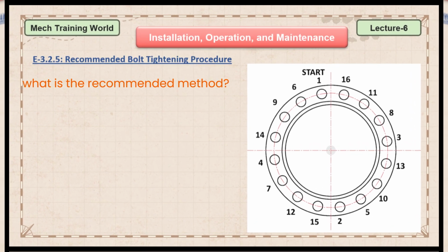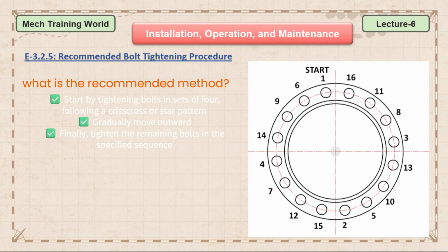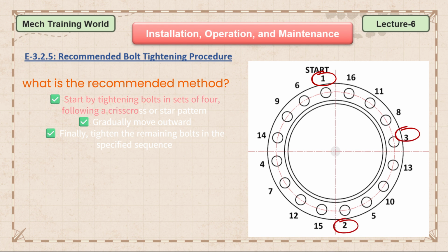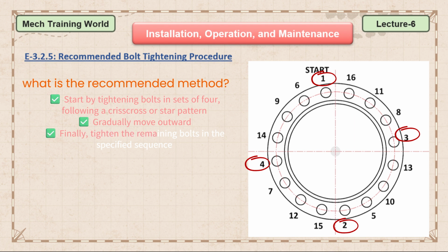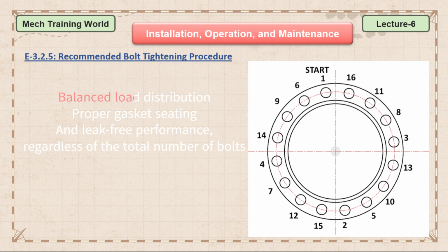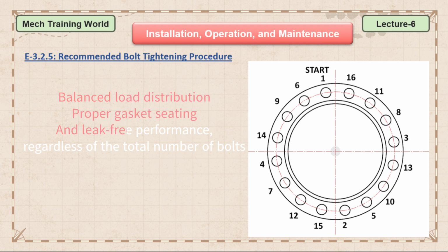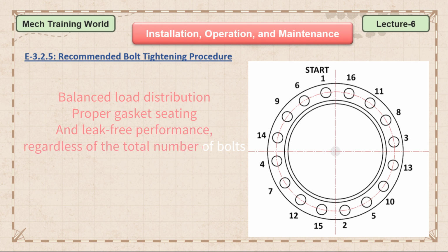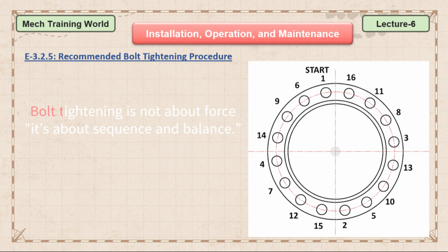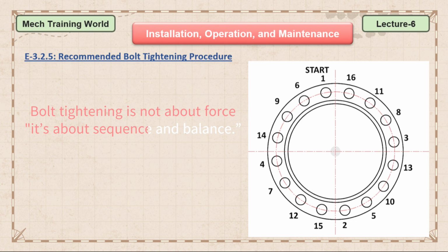So what is the recommended method? Start by tightening bolts in sets of 4 following a crisscross or star pattern. Gradually move outward. Finally, tighten the remaining bolts in the specified sequence. This method ensures balanced load distribution, proper gasket seating, and leak-free performance, regardless of the total number of bolts. Always remember, bolt tightening is not about force, it's about sequence and balance.